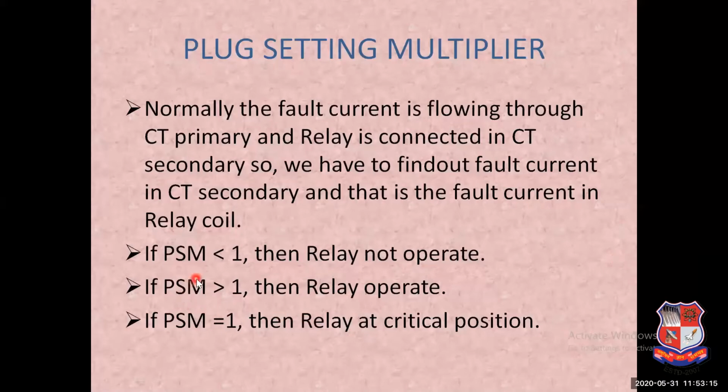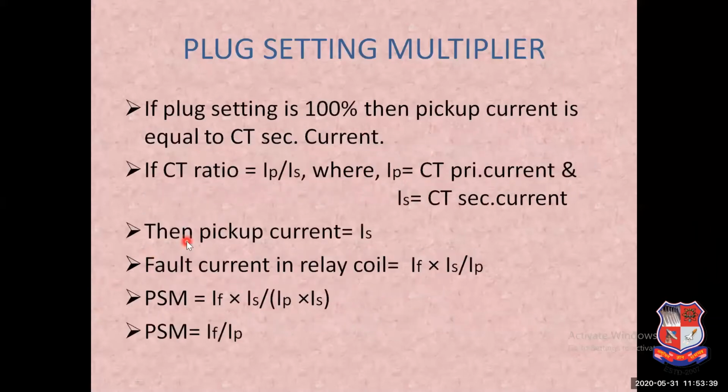If PSM is less than 1, then the relay does not operate. If PSM is greater than 1, then the relay operates. And if PSM is equal to 1, then the relay is at a critical position, meaning it is just ready to operate.